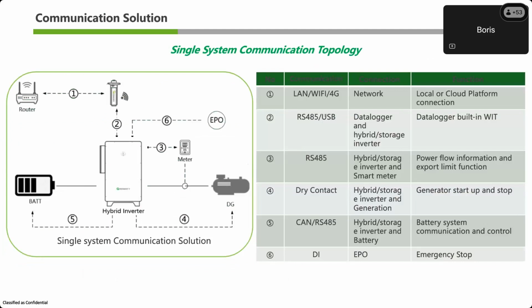Communication on the inverter. The inverter outputs its signals over Modbus RTU, and we have a Modbus register map that we're happy to share with our customers, which they can use to interface with any third-party EMS, or if they want to just have their own portal. The readout information is everything from the battery information, all comes from the inverter, and/or the inverter information. So PV, power, any voltages, you can keep that monitored 24/7.